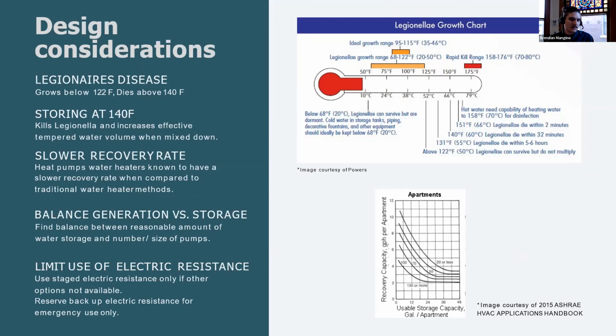You don't want too much storage. You can try to reduce the number of heat pumps by increasing the amount of storage, but that only takes you so far. Storage is expensive. If you're getting above 120 gallons, then you're paying for ASME tanks, and those get very expensive very quickly. They take up a lot of space, and you have increased standby losses.